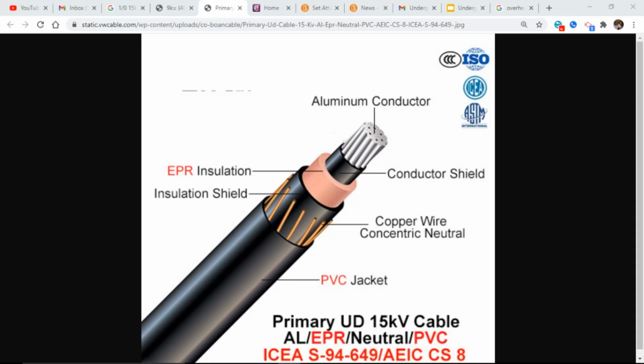Now, they've got it in red. There are different types of insulation that you can have around a conductor. I'm not worried about the EPR part; that is the type they're using here. But as long as you use insulation, your next part is an insulation shield. So you've got a conductor shield that goes around, insulation, then an insulation shield that goes around, shielding the insulation, the protector for it. Then a copper wire concentric neutral.